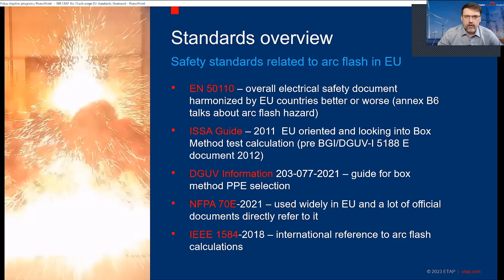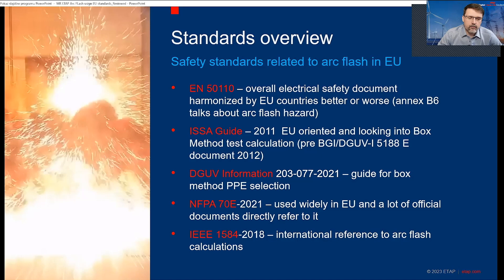The base standard in the EU is EN 50110. This is an overall standard about the electrical safety operation of general electrical installations. It is harmonized across European Union countries — better or worse — but it has Annex B6 about arc flash. There is also a guide: ISSA, the International Social Security Association, made a guide for arc flash hazard.